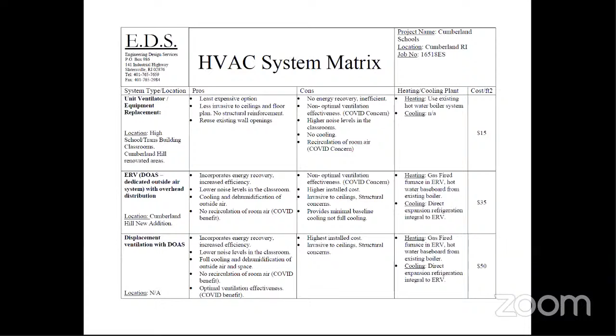What I thought I heard was, is there a difference in operating costs between these different systems? There certainly is. The unit ventilator replacement just brings in raw outside air, heating it with hot water and exhausting it through the roof. Both of the other options incorporate energy recovery, so you would be saving approximately 30% on your fuel costs for heating if you went with those.